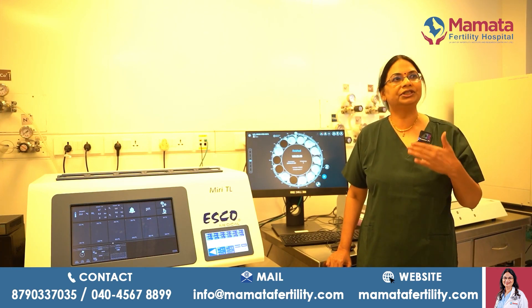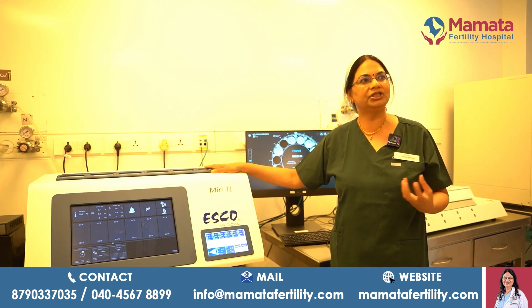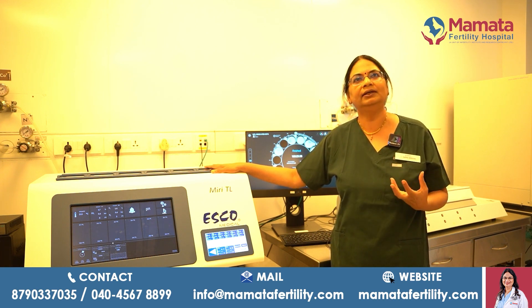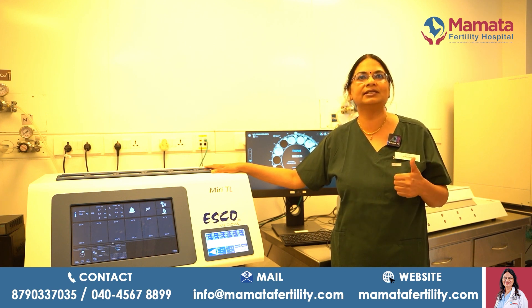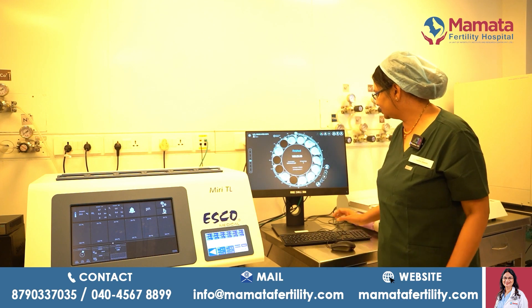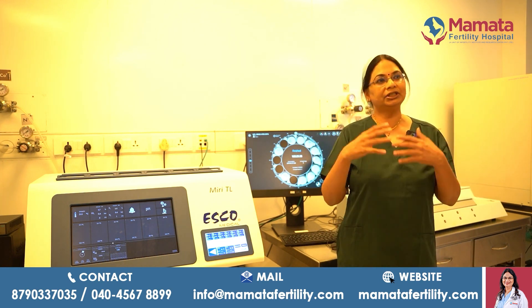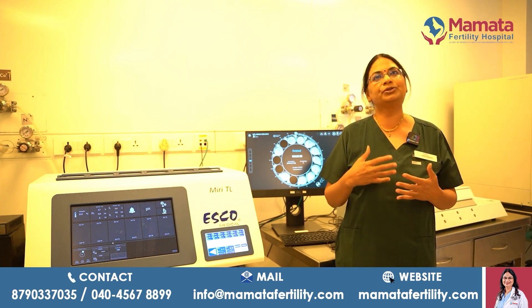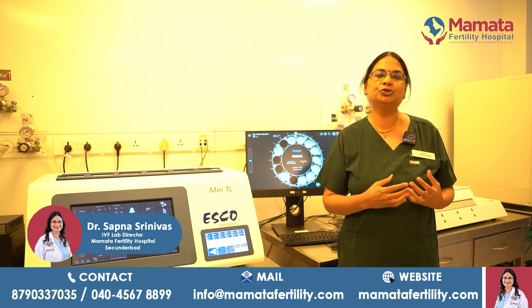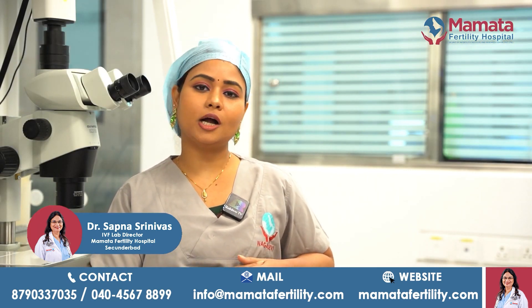Is there any advantage of using the time-lapse system in an IVF cycle? The first advantage is that the culture conditions are stable because we are not taking the dish out of the incubator — it is constantly being imaged inside. When we do not disturb the culture environment, we obviously get better embryo development, so embryos are of better quality. Secondly, because we have this continuous monitoring, as a team we can look at so many details the embryo goes through during this journey and select the most viable embryo for transfer to improve outcomes for our patients.